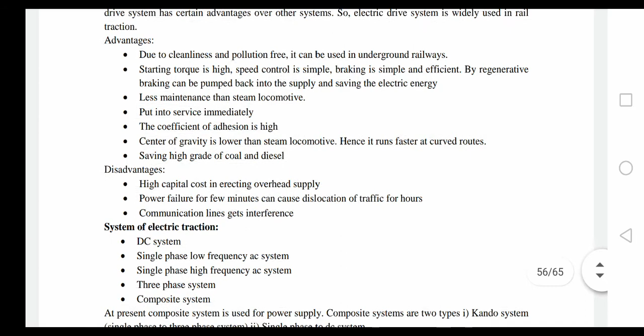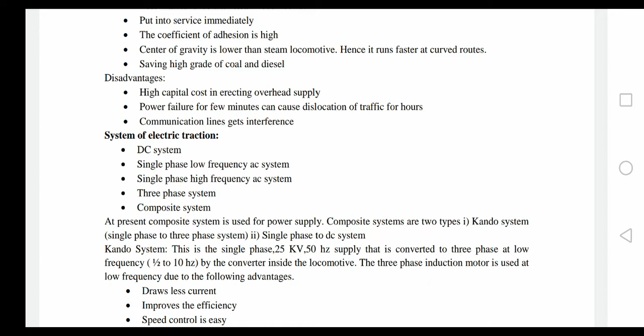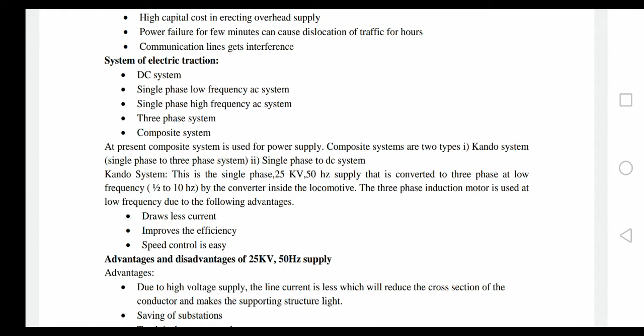In electric traction, we can use a DC system, a single phase low frequency AC system, a single phase high frequency AC system, a three phase system, or a composite system. At present, the composite system is used for power supply. Composite systems are of two types: the Kando system, single phase to three phase, and single phase to DC. The 25 kilovolt 50 hertz supply is converted to three phase at low frequency by the converter inside the locomotive. On top of the locomotive we have a converter box, where the voltage is changed from one level to another. The three phase induction motor is used at low frequency due to the following advantages: it draws less current, improves efficiency, and speed control is easy.